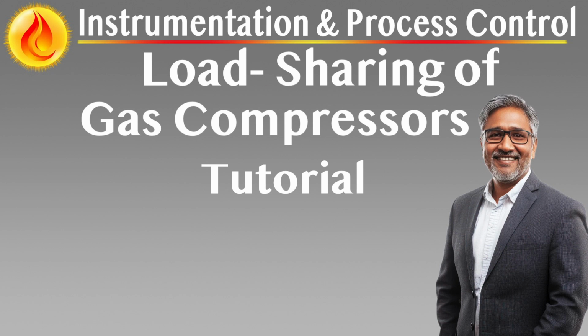Without intelligent coordination, compressors may recycle unevenly, causing mechanical stress, thermal imbalance, or inefficient load distribution. Recycle balancing solves this by synchronizing the anti-surge valve operations across all compressors, ensuring that no single unit is overburdened and that surge recovery occurs in a controlled, uniform manner. The result is a more stable compressor network with extended equipment life and improved energy efficiency.